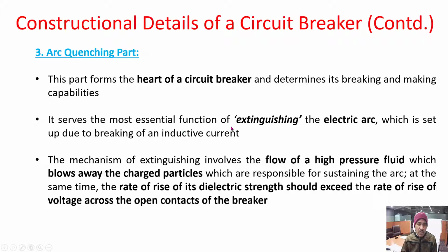So it serves the most essential function of extinguishing the electric arc, which is set up due to breaking of an inductive current. The mechanism of extinguishing involves the flow of a high pressure fluid which blows away the charged particles which are responsible for sustaining the arc. At the same time, the rate of rise of its dielectric strength should exceed the rate of rise of voltage across the open contacts of the breaker. So this is how we have to ensure the rate of rise of dielectric strength should exceed the rate of rise of voltage across the open contact.